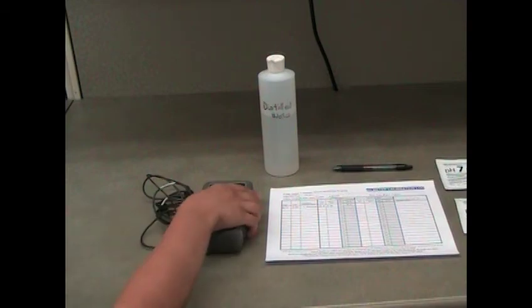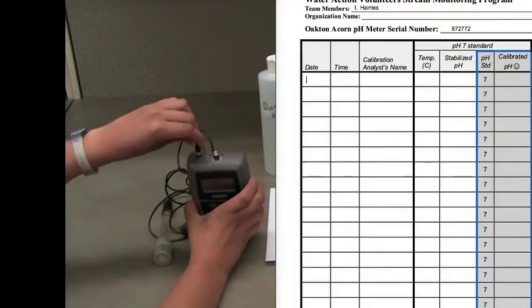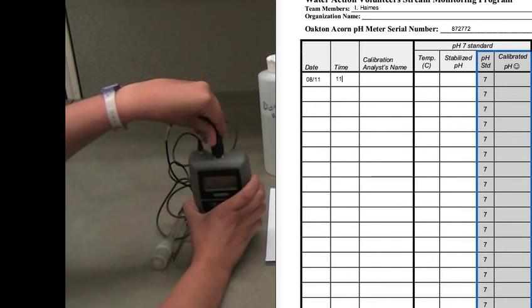Connect the pH and temperature probes to the meter and turn the meter on. Press the MODE button to enter pH mode if necessary.